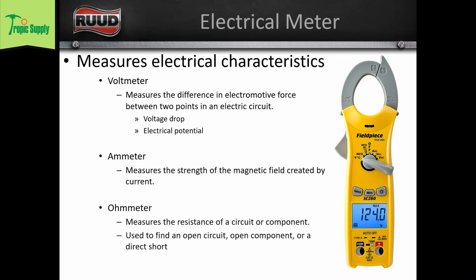And an ohm meter. What's the difference between a 75 VA transformer and a 40 VA transformer? And don't say 35. How much current it can handle, and how much load it's putting out. I have a whole class that we could do specifically on transformers and voltage drop and what they mean, and we can certainly schedule something like that. But if you are just replacing a 40 VA transformer with a 75 VA transformer, you might be causing problems, right? You might think you're solving the problem at hand, but you might be causing some other issue downstream.